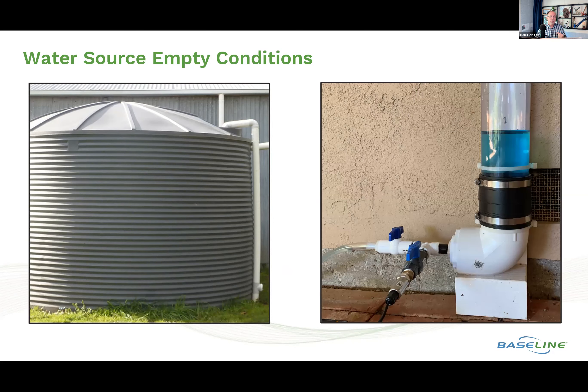Pressure is another way to detect tank level. I'm showing the pressure transducer on the same test rig — the BL-5406 transducer. What's nice about using pressure for tank leveling is you just need a threaded connection. At one pound of pressure the tank is empty; at ten pounds it's full. You can see across the entire range based on pressure, compared to the narrow window of a soil moisture sensor.